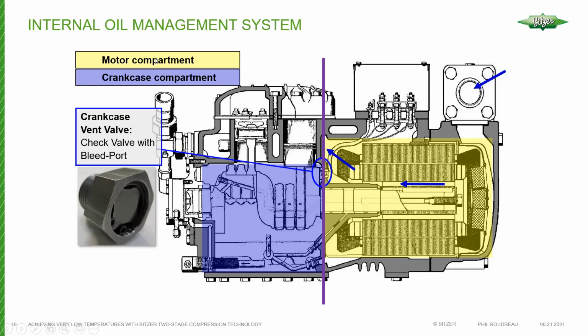But similar to the single stage compressors, we use these crankcase vent valves on the partition, and also there is an ejector at the bottom of the compressor in the crankcase to return any oil that is entrained in the refrigerant that comes back from the suction line, drops out of suspension, ends up in the bottom of the motor barrel, and then the ejector can bring that back into the crankcase.